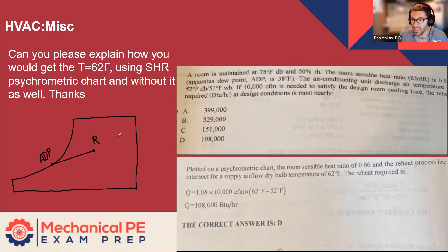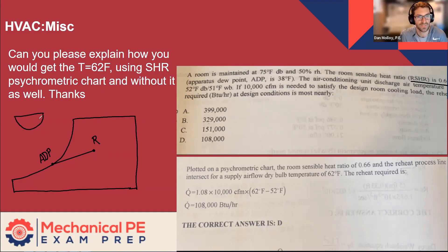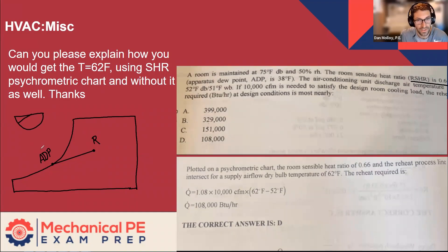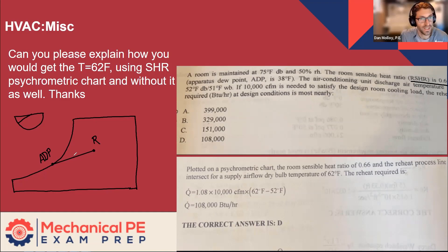Another way to communicate the same information: there used to be a protractor on the psychrometric chart where you could figure out the sensible heat ratio if you knew the sensible and latent load and the total load, and then you could draw a line on this protractor. When it was paper and pencil, you could move the protractor onto the chart and draw a line parallel to that line, and you would know you've got exactly the right room sensible heat ratio.